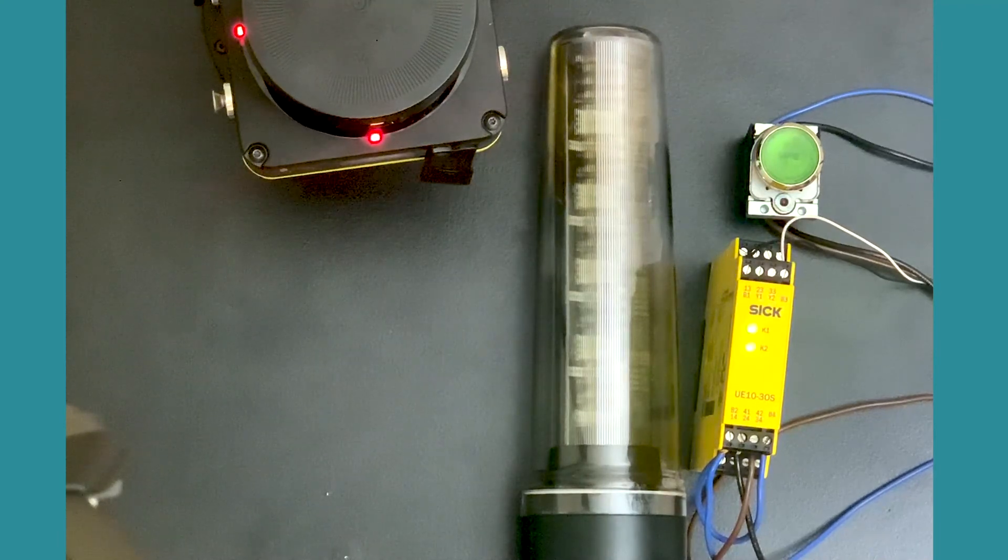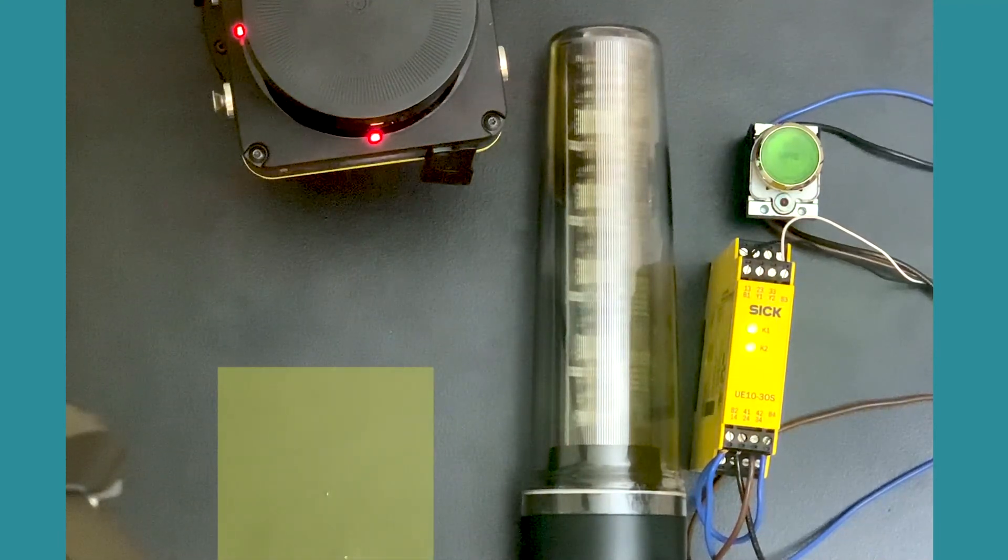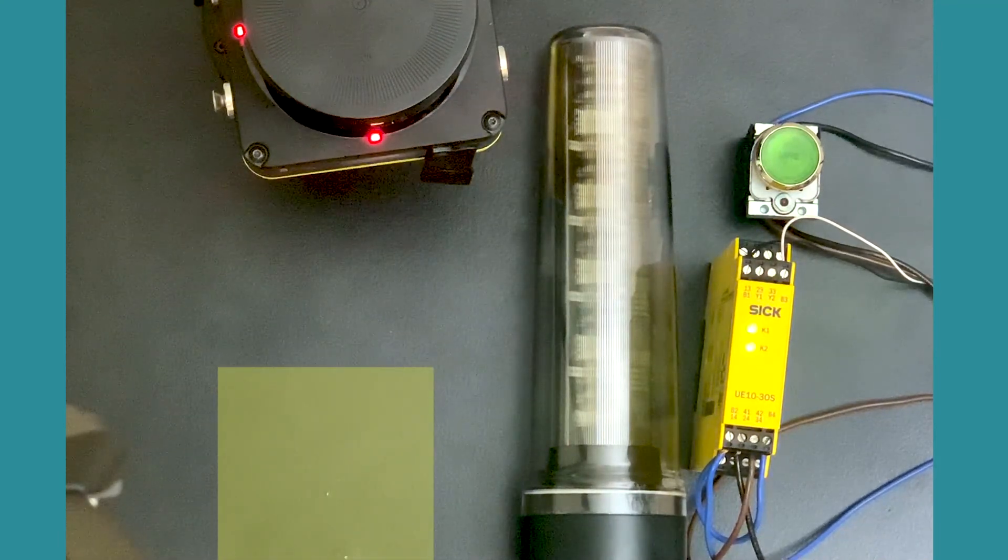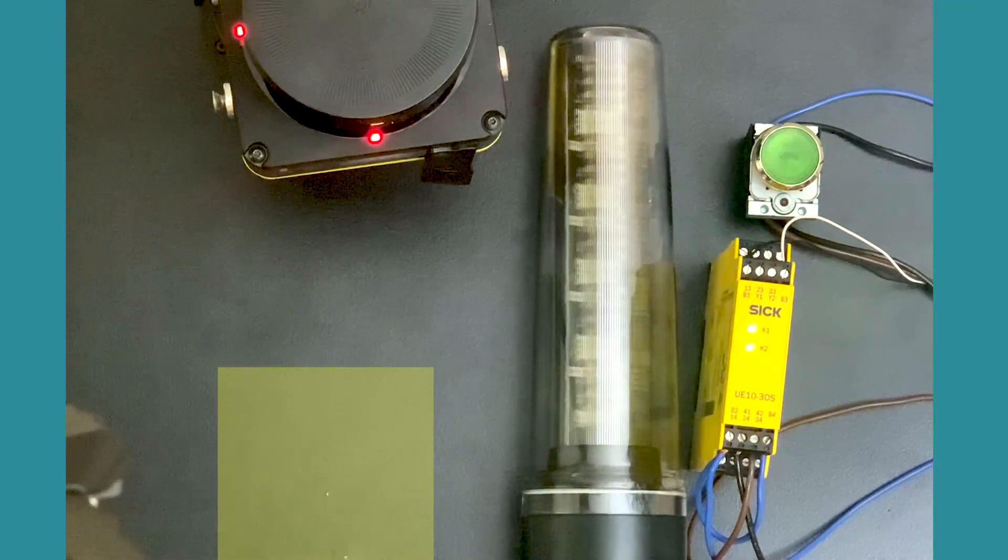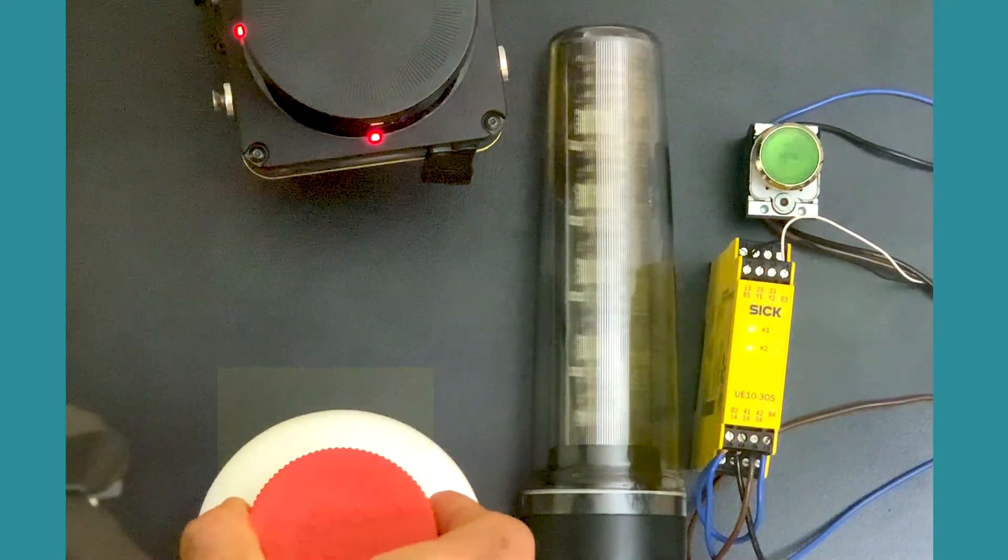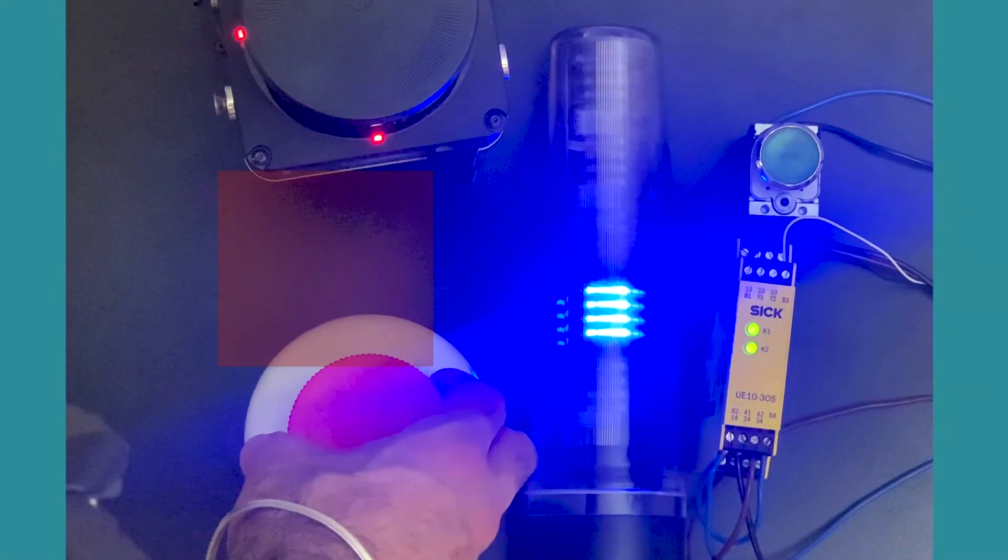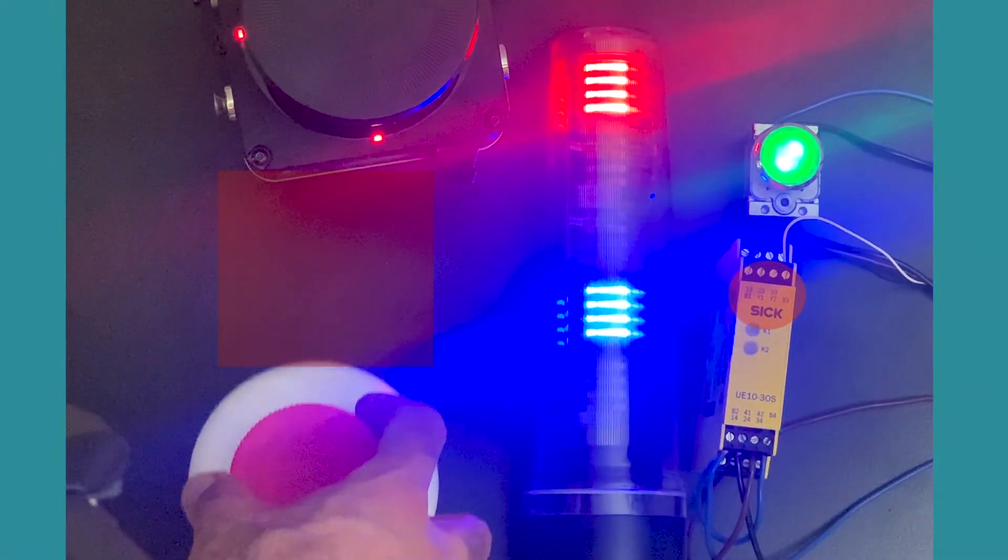So if anything enters the warning field, a blue light and a buzzer is turned on. And if it moves further into it and enters the protective zone, the red light turns on and you will see the relay de-energized and the equipment shuts off.